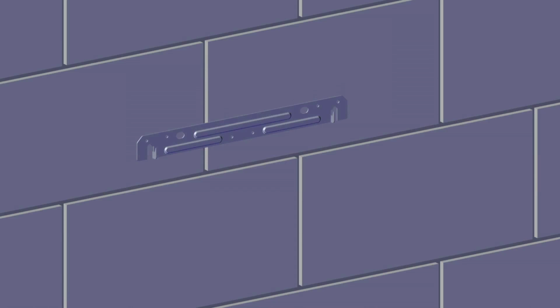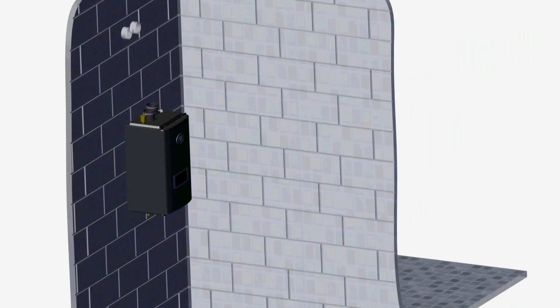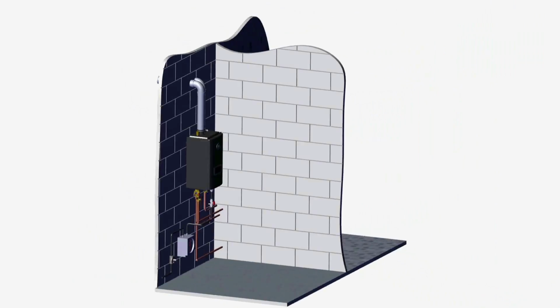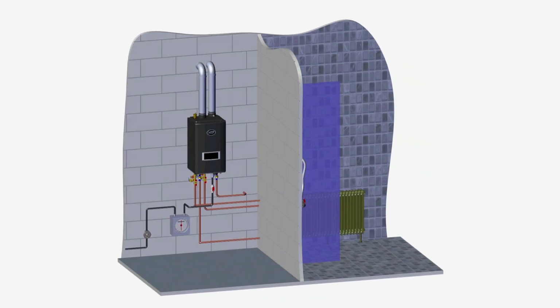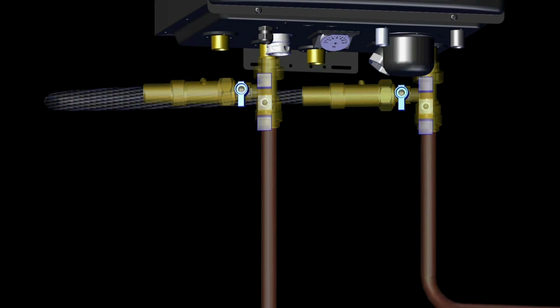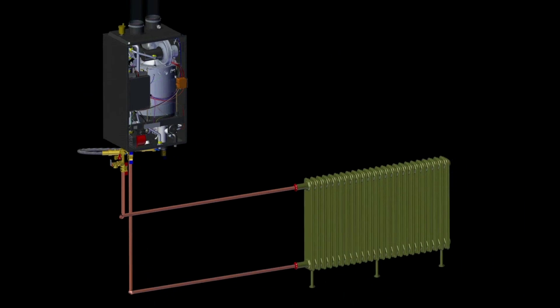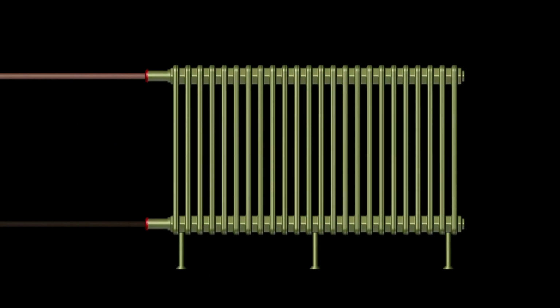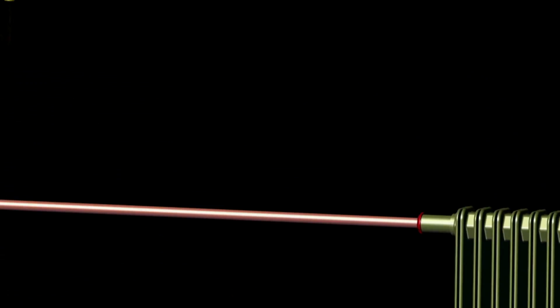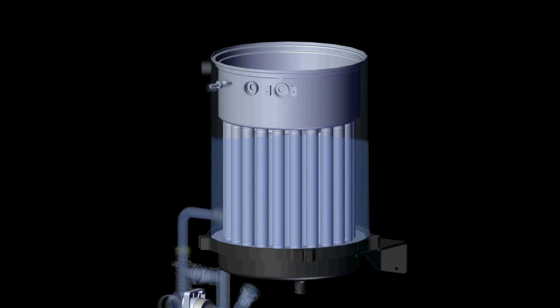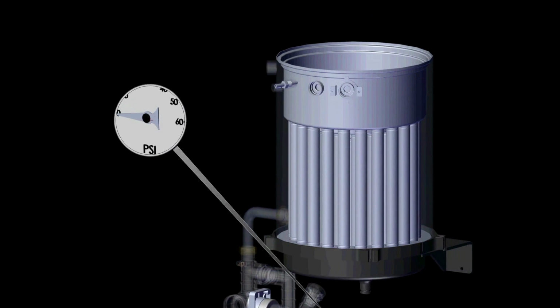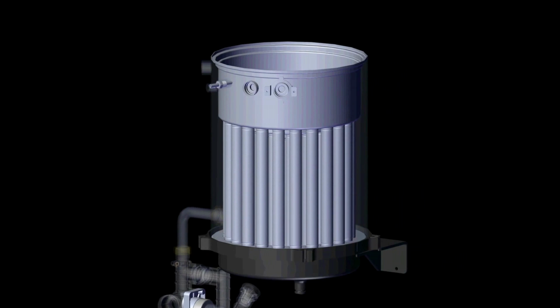You can install the product on the wall of the boiler room where flue tubes and water pipes can be easily assembled. Push the power button to operate the boiler. If the system is not supplied with enough water or air is trapped inside the heat exchanger, error code 80 will appear. Ensure the valve on the auto feed line is open or connect a hose between domestic cold water inlet and heating return lines to fill the system with water. When water is supplemented in the heat exchanger, the water level sensor operates normally and 15 psi water pressure is reached.